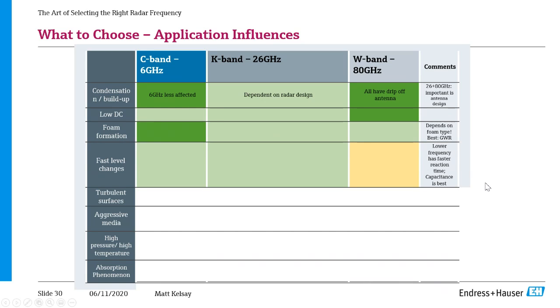If you've got a process that changes level very fast, again, your lower frequency is going to be better there, as the high frequency has a slower reaction time. But if you've got a very small vessel, something like a little filling bowl, if you're in the food and bev industry, a capacitance probe is going to be your best bet. That's the absolute fastest reaction time you can get out of a level device. And again, that's part of the reason why we keep around all these different technologies and styles.